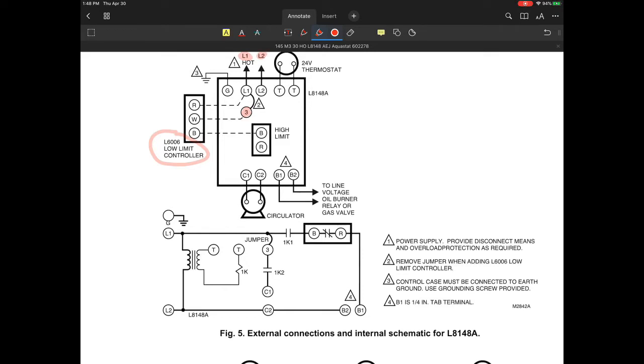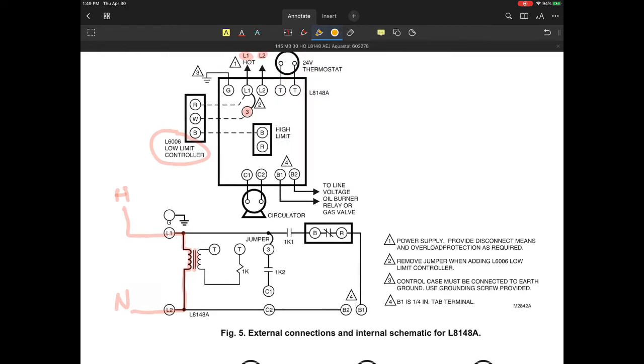So let's take a look at the internals on this device. This line voltage one is by far the simplest of all of these controls. When we look at an application like this, I've got L1 that's going to feed my hot. As soon as I power from the hot terminal to the neutral terminal on L2, I am powering this tiny little 20 VA transformer. Nothing much on this system at all.